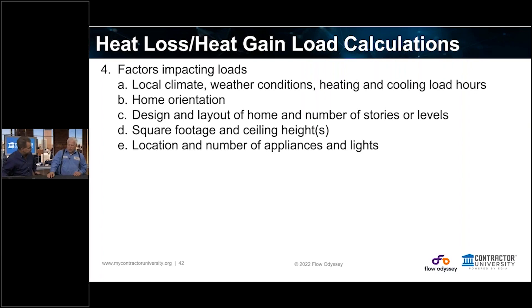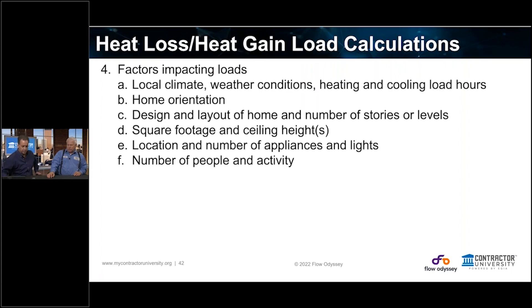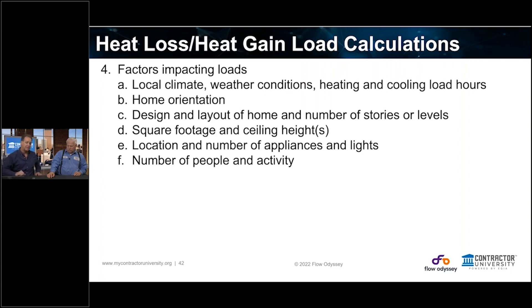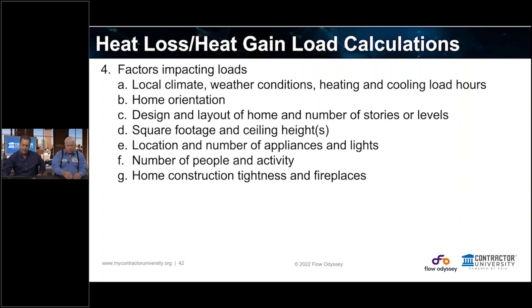We did an LED changeout in one commercial building and went from 27 tons to 14 tons. Number of people and activity level matters too — we give off about 230 BTUs sensible and 200 BTUs latent at rest, but at a gym or retail facility that jumps up to 700 to 1,000 BTUs. The construction — what is the home made of? The insulation factors, whether it's drywall or plaster, what type of glass, and the tightness of fireplaces, because that's going to allow for infiltration and exfiltration.